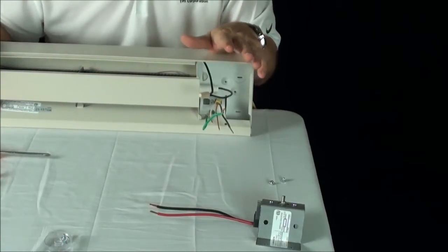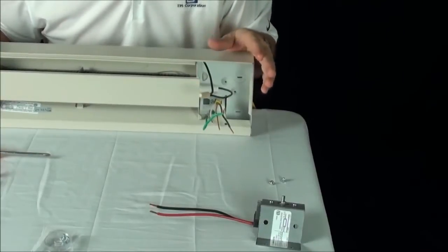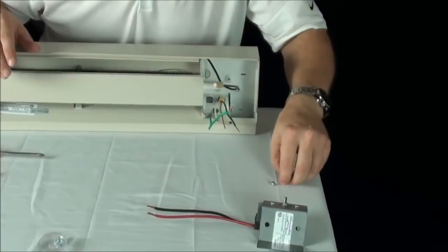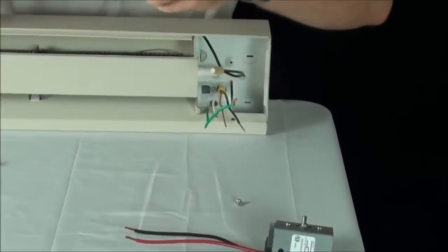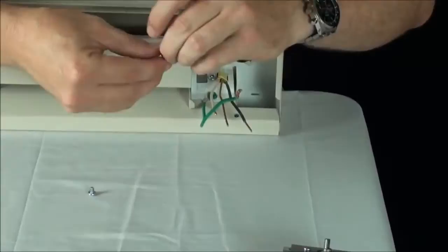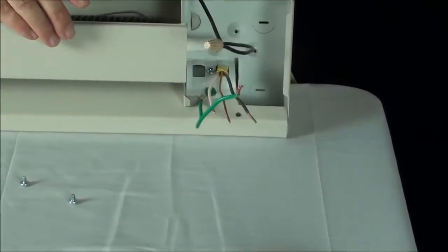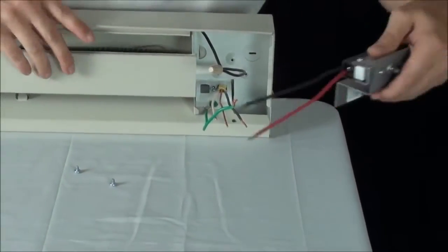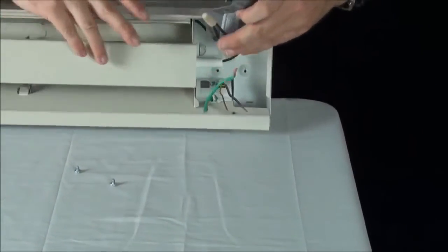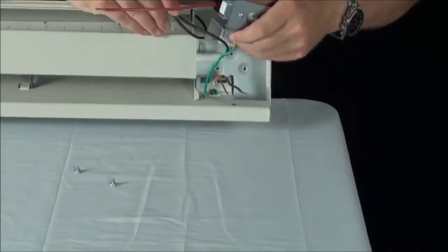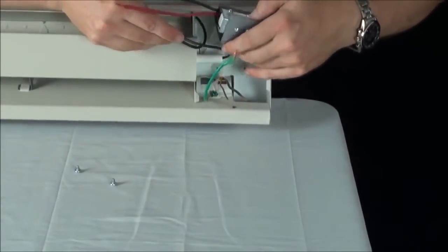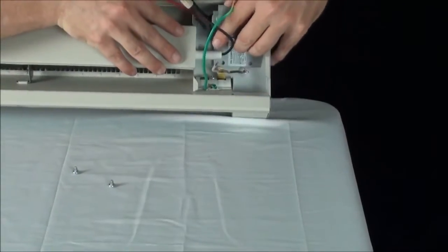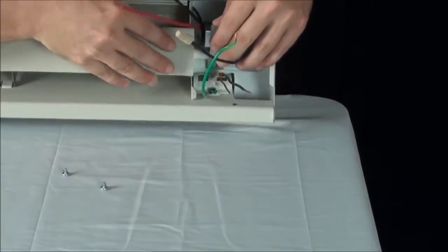Today we're going to hook up a single pole thermostat to a 2900 series TPI baseboard heater. First thing you want to do after you have your heater installed and the power wire coming to your heater, you want to install your thermostat by sliding it behind the protruding part of the element. You will have two mounting screws that come with the thermostat.